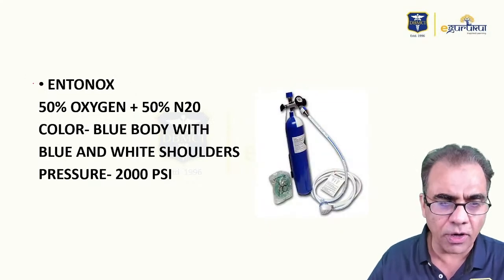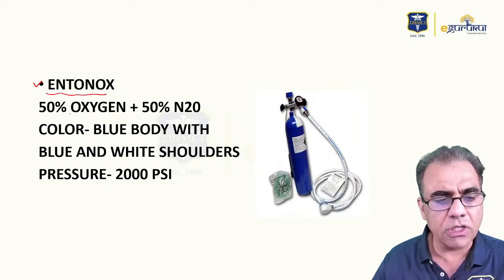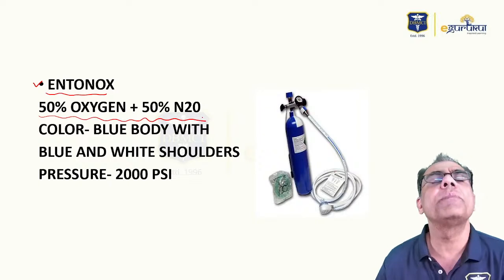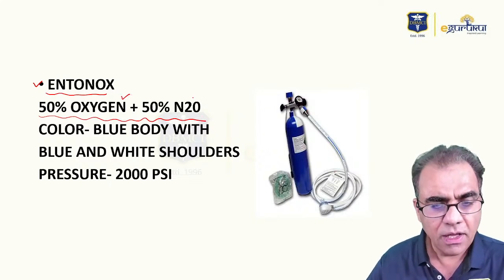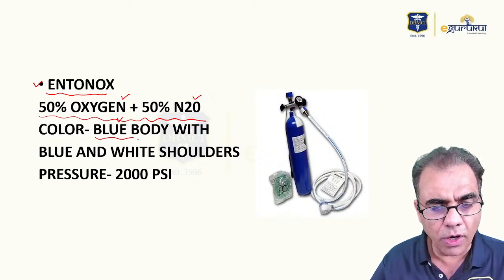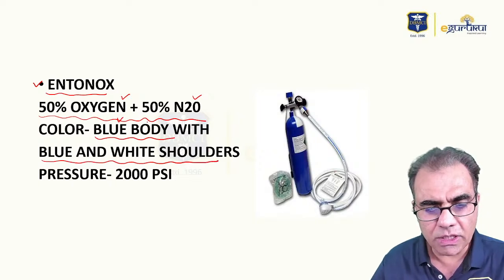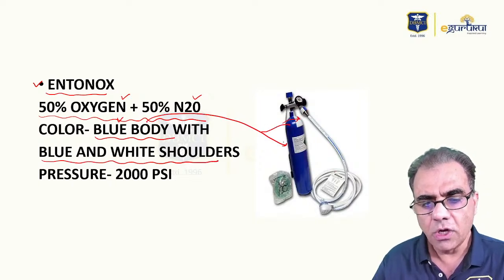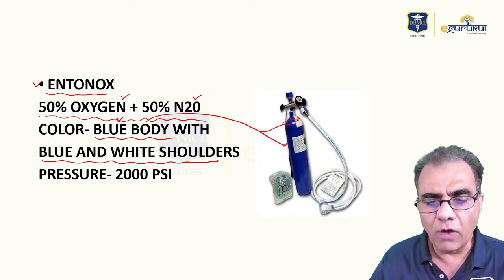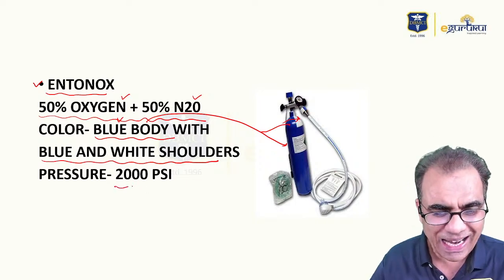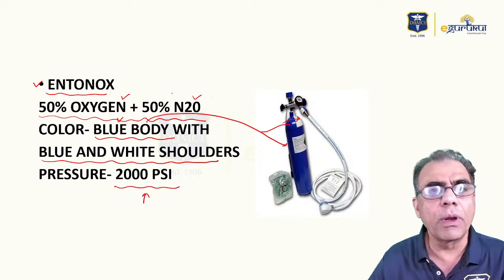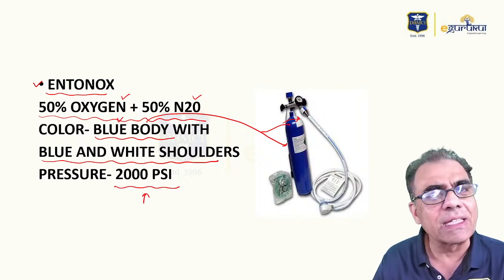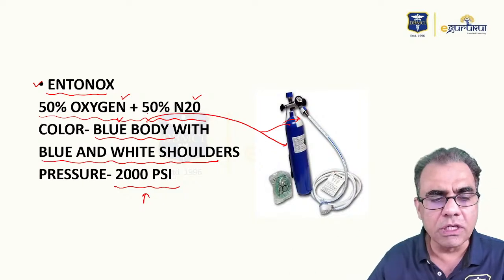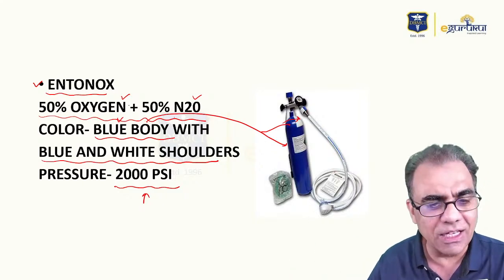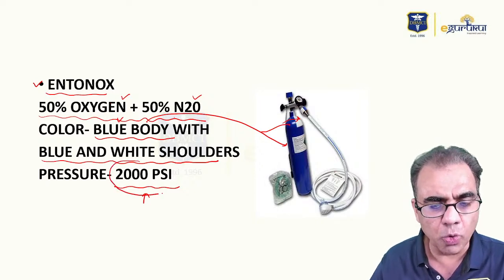The third important cylinder is Entonox. Entonox is a mixture of 50% oxygen and 50% nitrous oxide, so half oxygen and half nitrous oxide. The color is blue body with blue and white shoulders. Blue shoulders indicate nitrous oxide, while white shoulders indicate oxygen. And the pressure is again 2000 psi. Why? Because of a simple rule of physics: when you mix two gases with different pressures, the combination will always exhibit the pressure of the higher gas. Nitrous oxide pressure is 760, oxygen is 2000, so the total pressure will be 2000 psi.